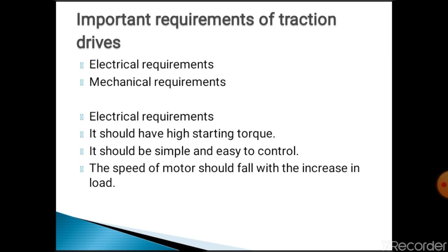For electrical requirements: it should have high starting torque; it should be simple and easy to control; the speed of the motor should fall with an increase in load; it should have series speed-torque characteristics; it should have a smooth braking system; it should be capable of carrying overloads in an emergency; and it should be capable of withstanding voltage fluctuations and temporary interruptions in the supply without any interruptions.